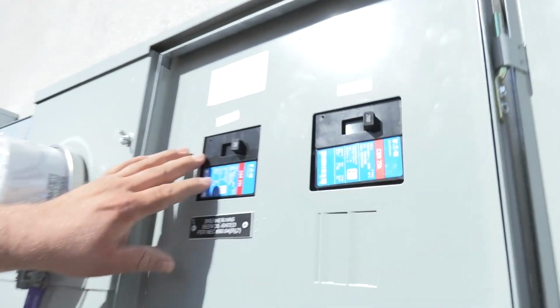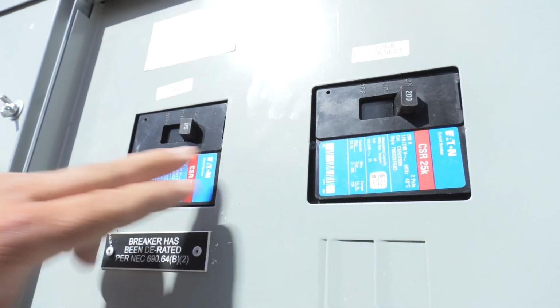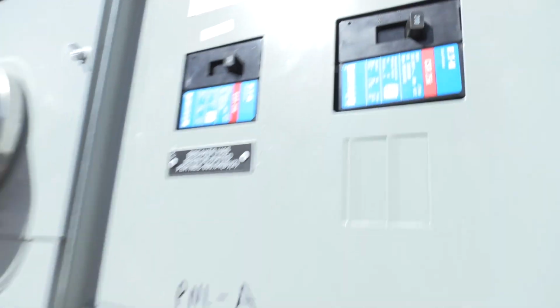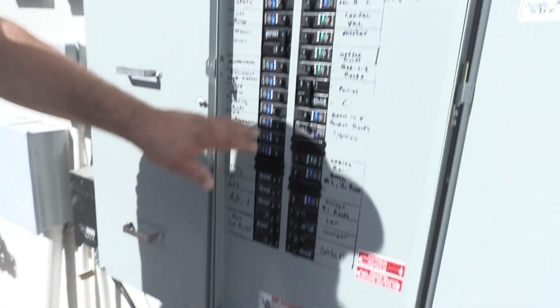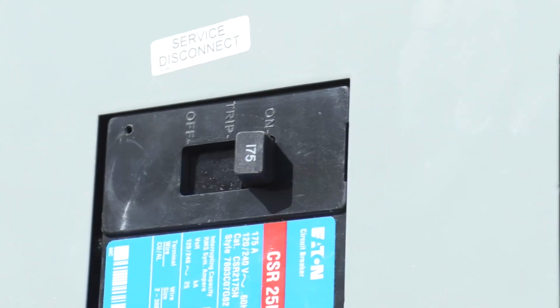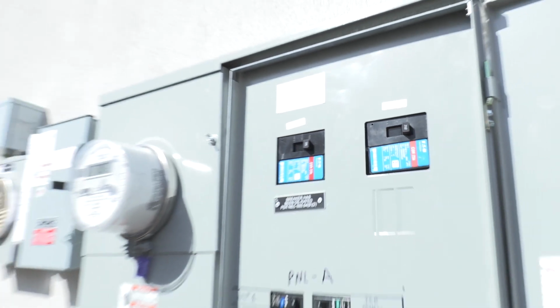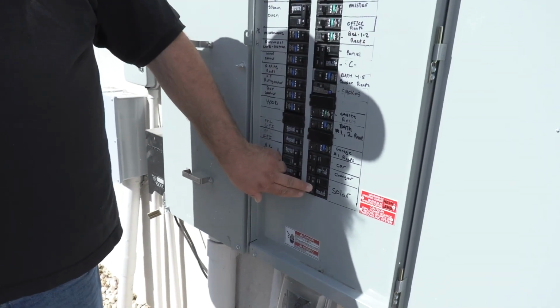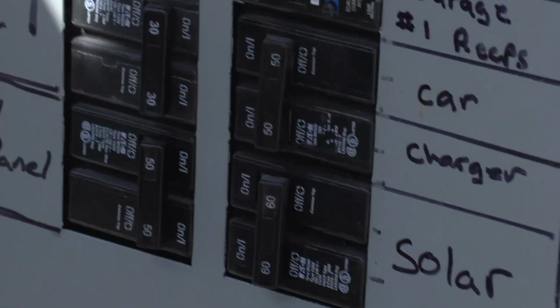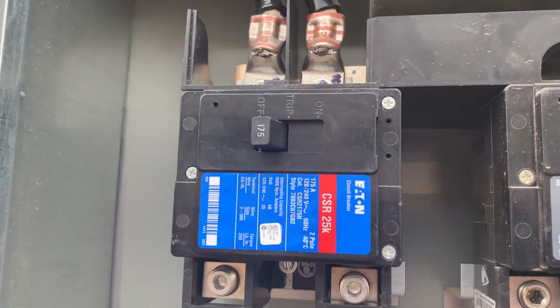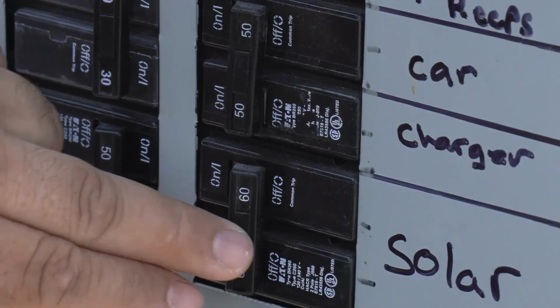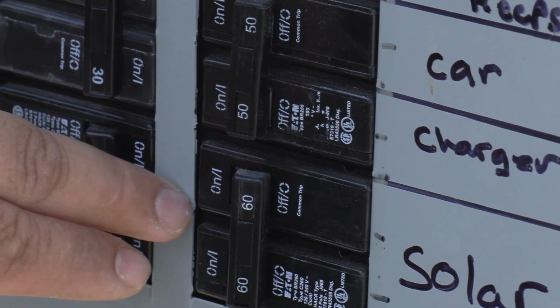I mentioned how this is derated. Normally you have a 200 amp breaker, just like this breaker would be in this spot. The busing right here, which is what all the breakers attach to, is rated for 200 amps. To code, the input current you can have on that busing can only be 120%. Since our array is a bit bigger than that, we wanted more solar. We have a 60 amp breaker here. In order for us to put that in, we actually changed this breaker to 175 amps. So 60 amp breaker here for solar to handle our system.